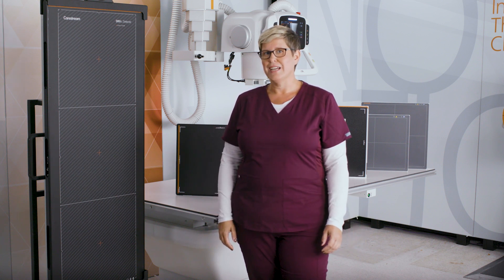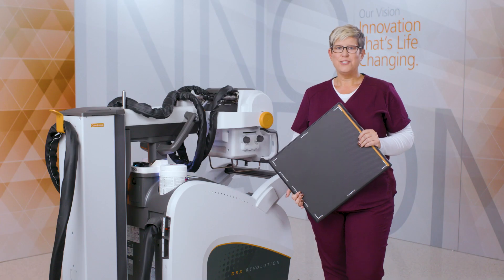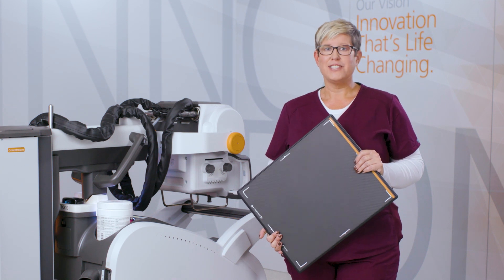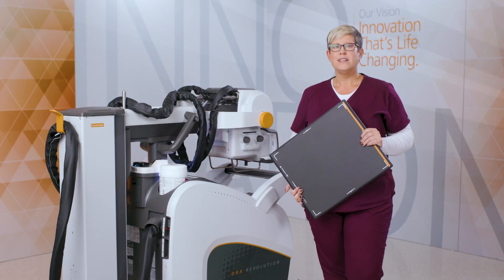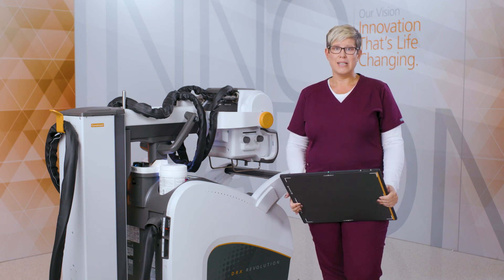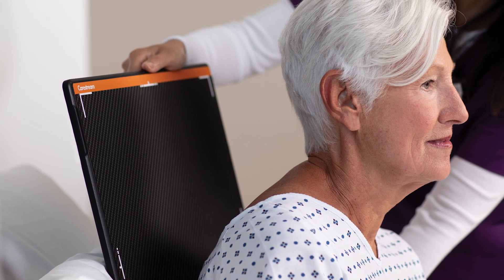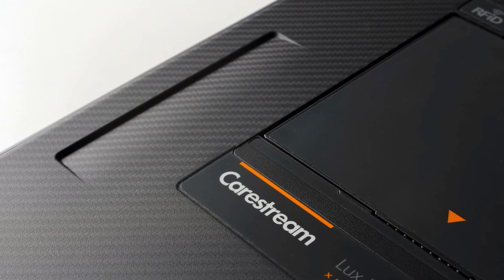Let's take a closer look at the different detectors and the features of each. The Carestream Lux 35 detector is our newest innovation in detectors for the medical market. This breakthrough detector has a sleek new design and is our first non-glass detector, resulting in a lighter weight compared to DRX+. Design improvements make this the ideal detector to use with your mobile x-ray system to reduce stress and complexity for radiographers while maximizing comfort and care for patients. Rounded edges slide easily behind or under a patient, reducing discomfort. Built-in finger grips help reduce tech fatigue, especially when doing mobile exams.